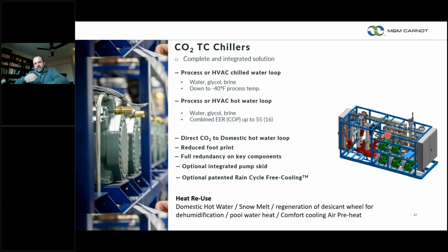This isn't the chiller that I just showed you in the other picture, but these are our chillers for transcritical carbon dioxide refrigeration. And the first one where we actually did heat reuse, we were able to make domestic hot water. We had a heat exchanger for a snow melt system in this building. One of the requirements of a hockey arena was an enthalpy wheel to dehumidify the space, so we used one of those heat exchangers to regenerate that desiccant wheel for dehumidification. We also had a heat exchanger for pool water heat. And there were a few spaces in the building where we could do comfort cooling air preheat with the heat exchanger that we provided. So it was a pretty unique application where the chillers were selected to make the ice for the ice arena, but also, instead of rejecting that heat outside, we were able to use it in a useful way throughout that facility.